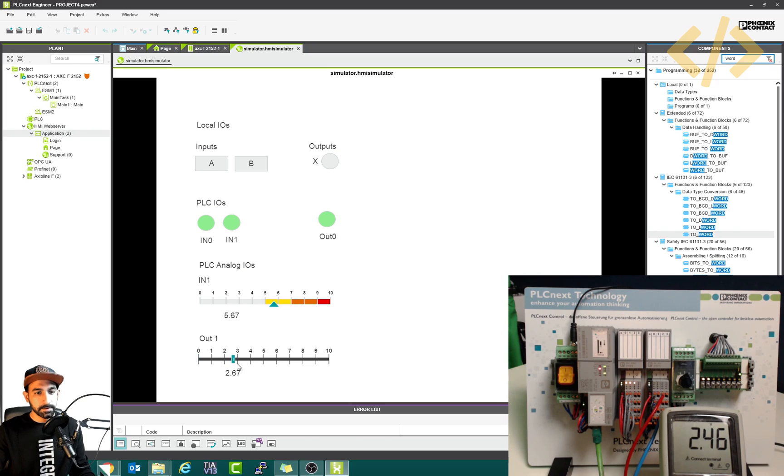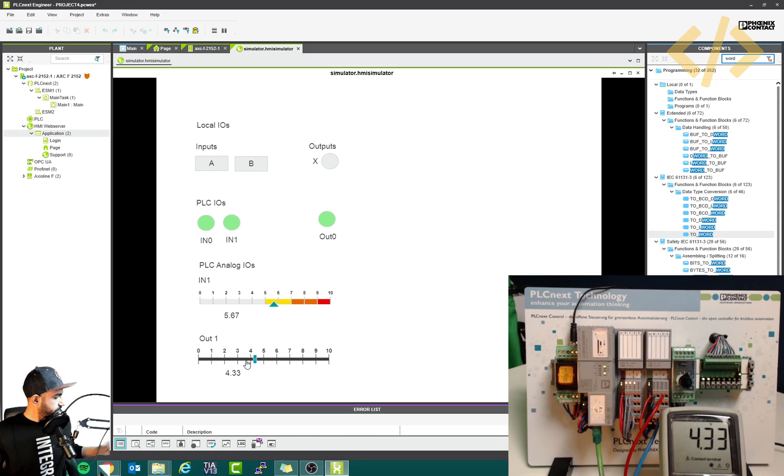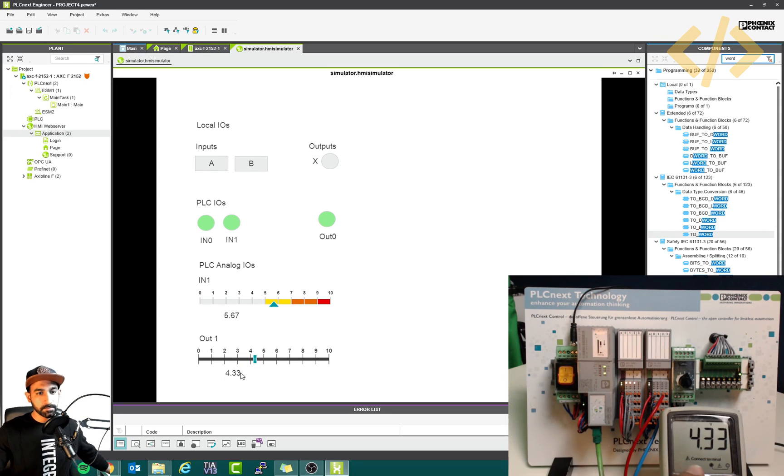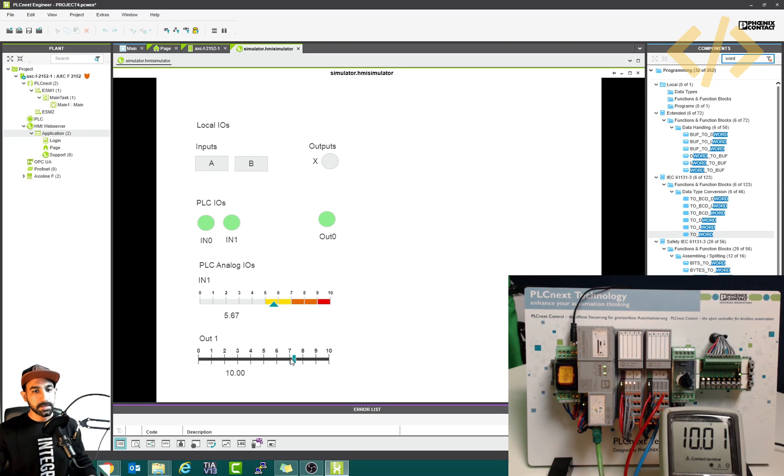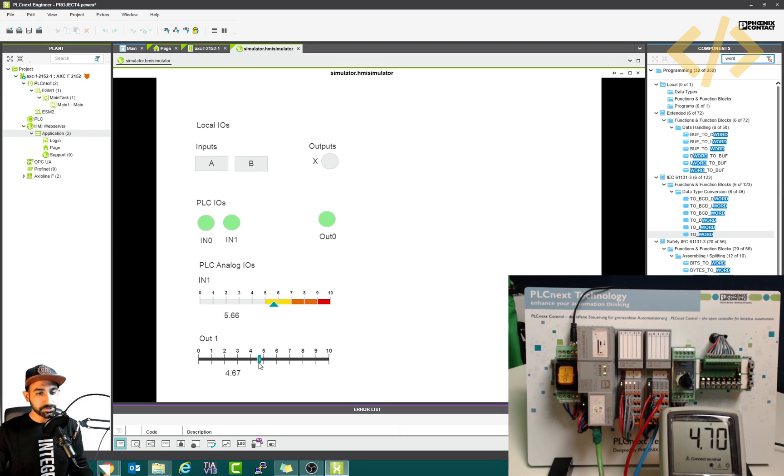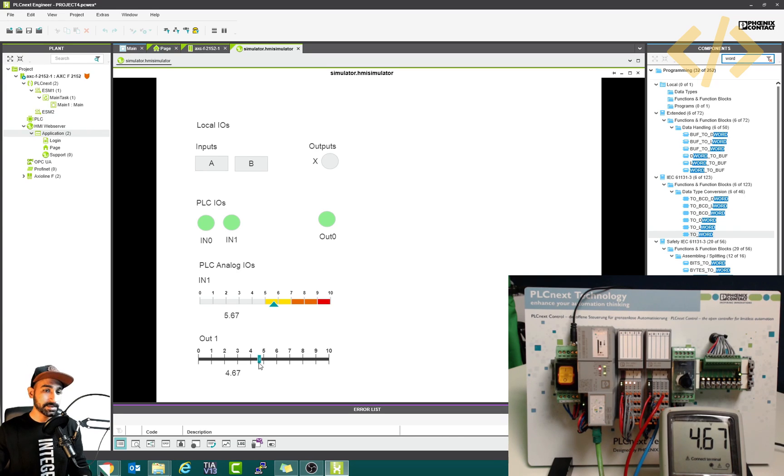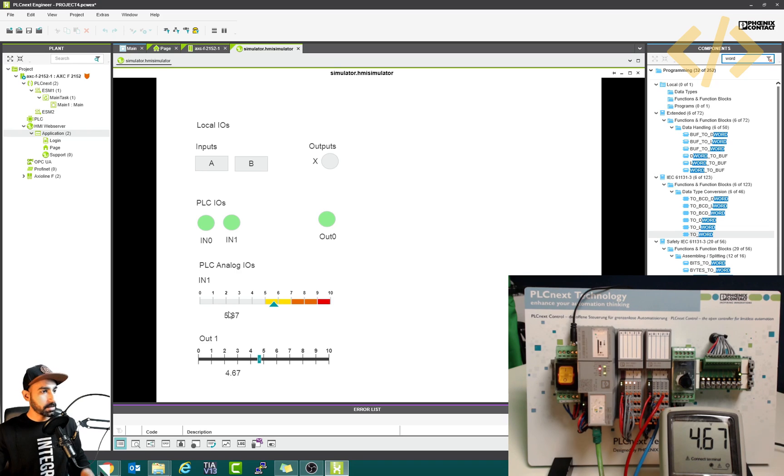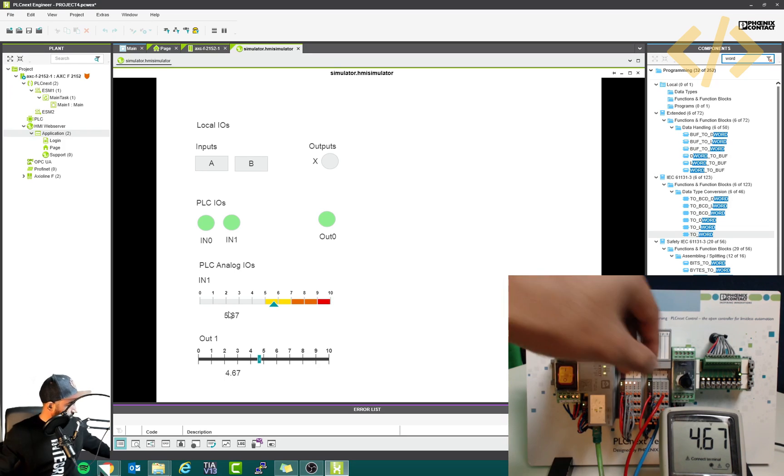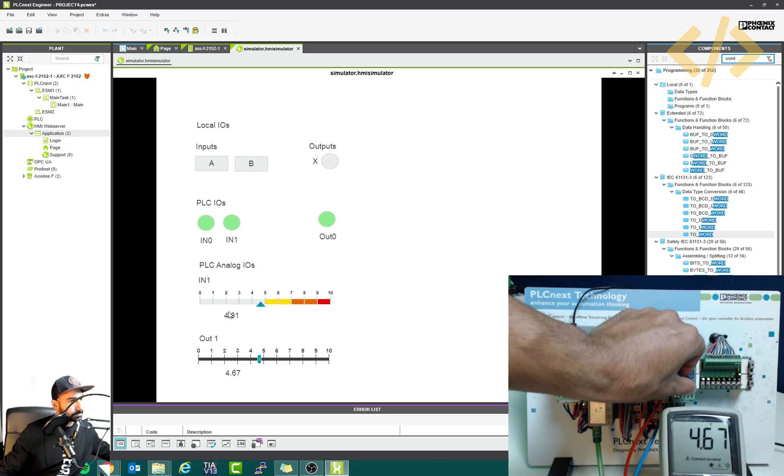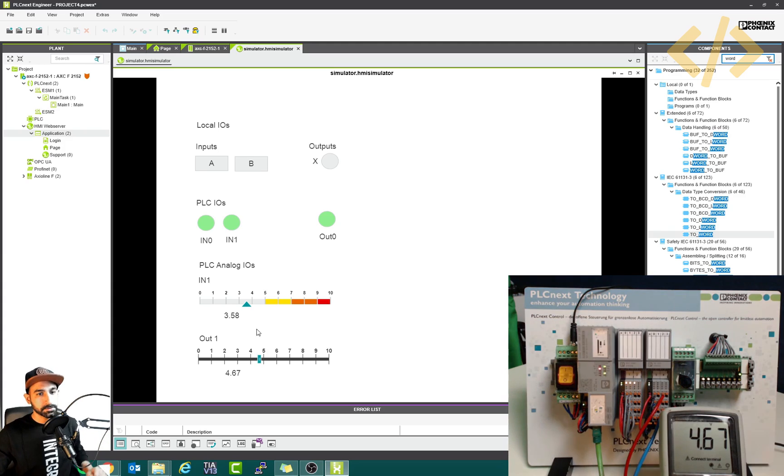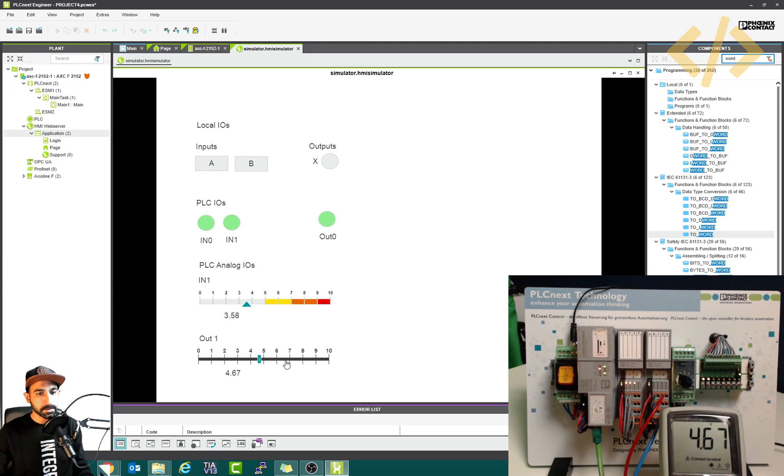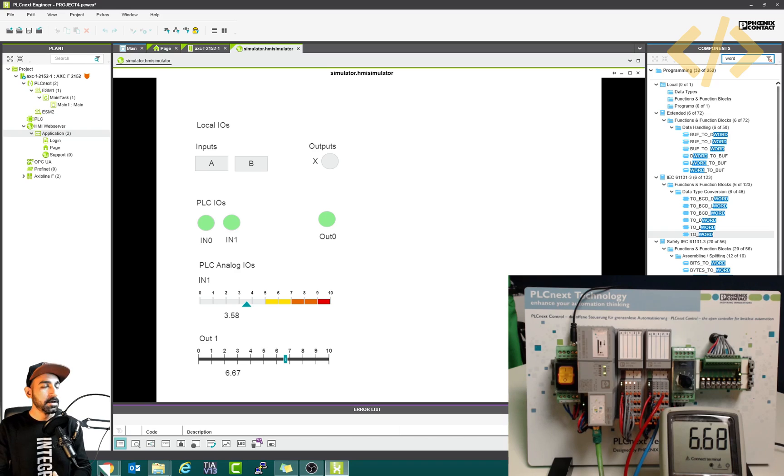Alright, now you can see if I move the slider, we have some values in our multimeter. You can see it's coming in voltage 4.33 volts, six volts approximately, and up to 10 volts. So that's how you can give the voltage from the HMI to your analog output device directly. And you can show the scaled value here. So analog input is coming here, and also change your 3.58 and output is shown on the multimeter.